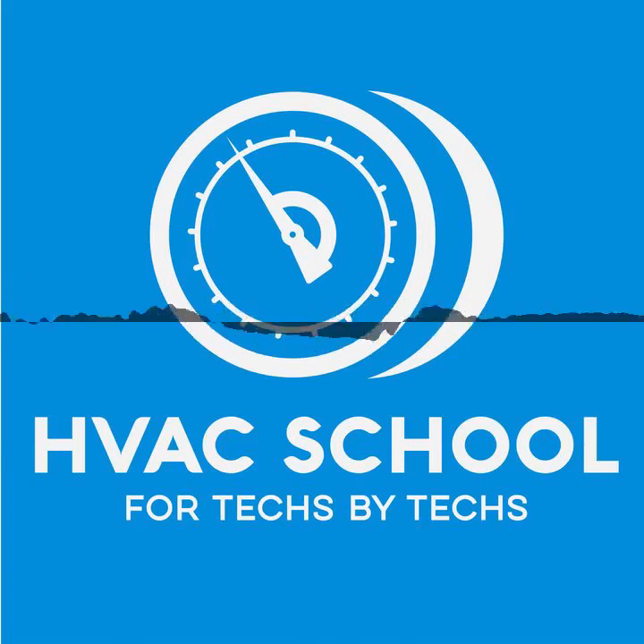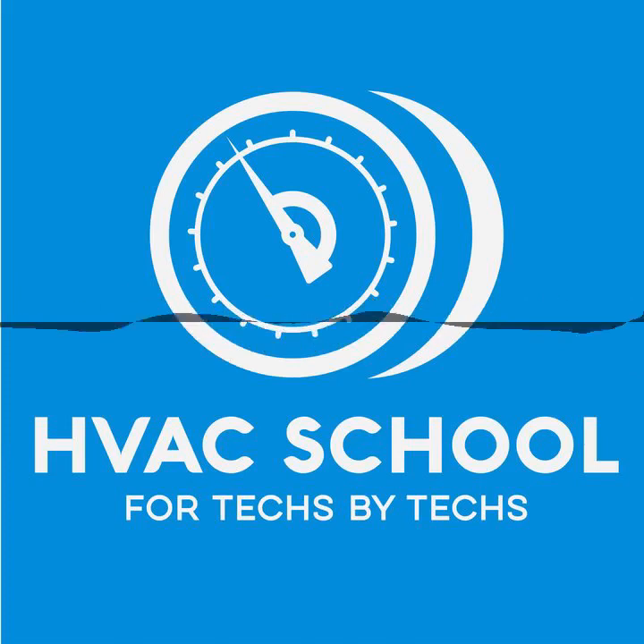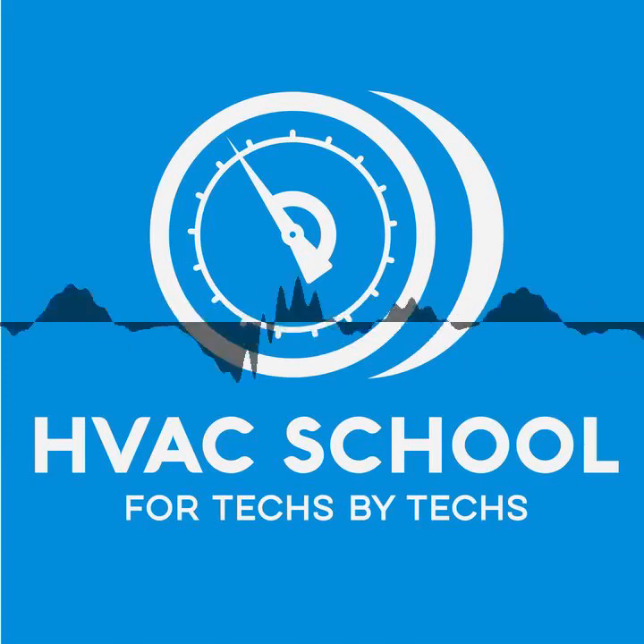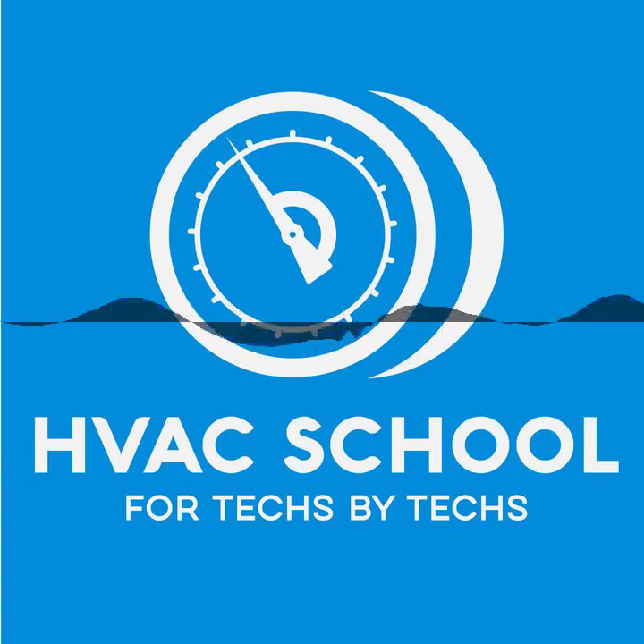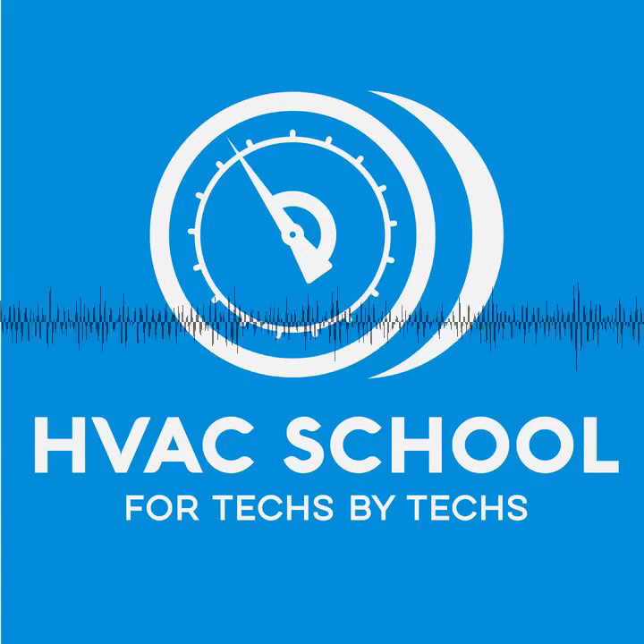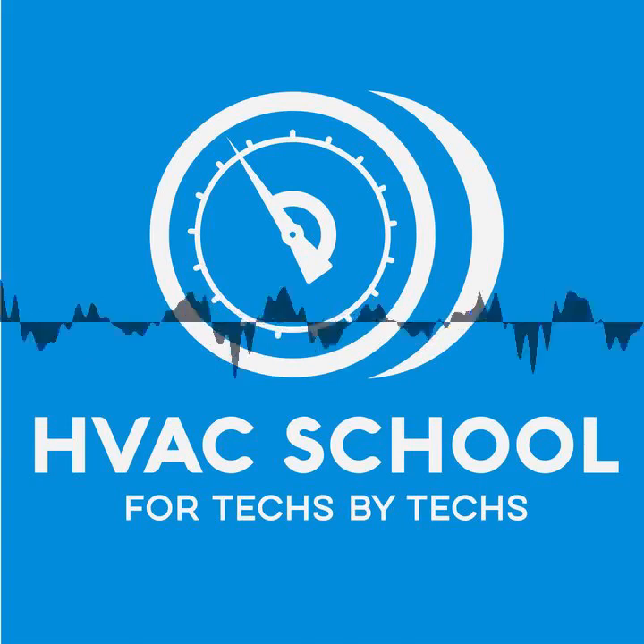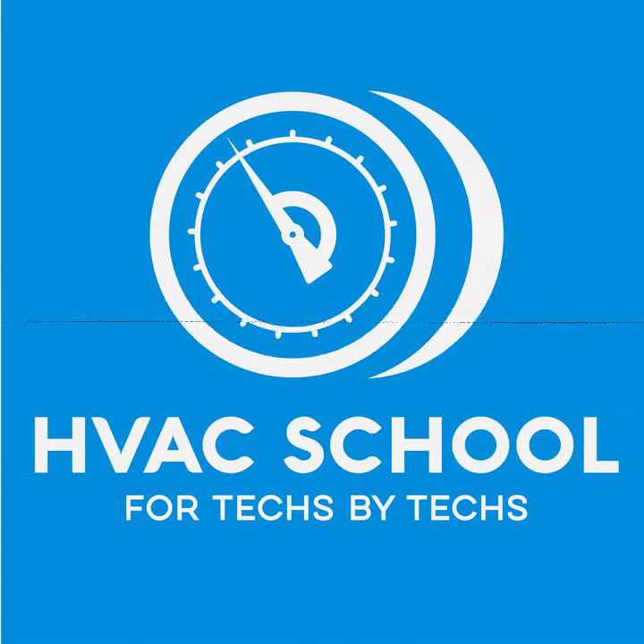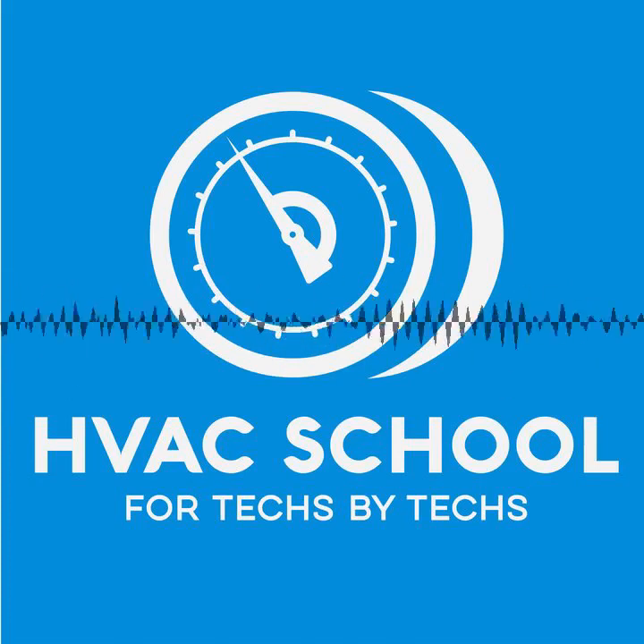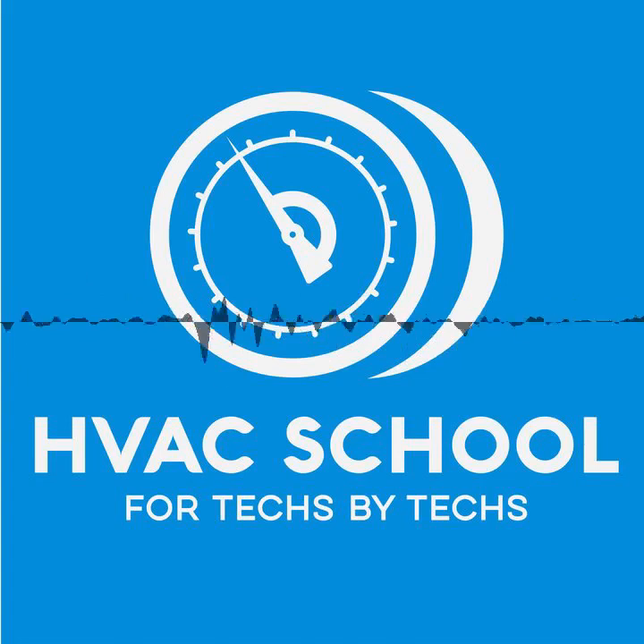Okay, so you've mentioned AEV. You just went there. Let's talk about AEV, because I think I've only worked on maybe three automatic expansion valve systems in my career, and that's what we're talking about here, right? Yep, I haven't seen one on a reach-in wine box. A lot of reach-ins are still cap tube, but we'll get into it anyway because you might see one on a bigger reach-in. But typically I've only seen them for wine, and it's basically a TXV is regulating superheat, and an AXV is regulating suction pressure if we want to really generalize it down. I know you have a whole podcast on TXVs that people should watch if they really want to know how TXVs work, but AXV only cares about suction pressure. You set it, and that's what it does.